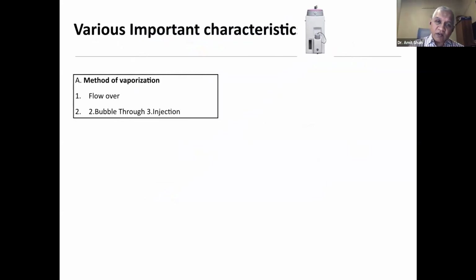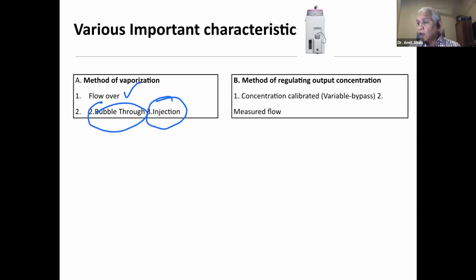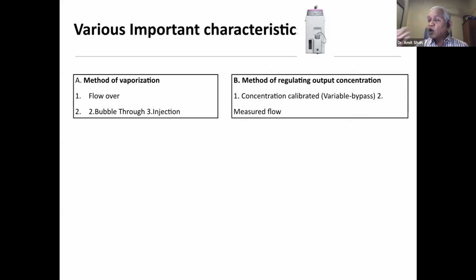So if you have to identify and classify a vaporizer, we can classify on the basis of 5-6 main important characteristics. One is the method of vaporization. First is flow over, which we have already seen. There are some which are bubble through, and in some there is a direct injection of vapor into the carrier gas. Okay, these are the 3 types of vaporization systems. Method of regulating output concentration: one is variable bypass. Second is measured flow. I'll explain how measured flow works. There's one older version of vaporizer which has a measured flow, and some new ones also have a measured flow.